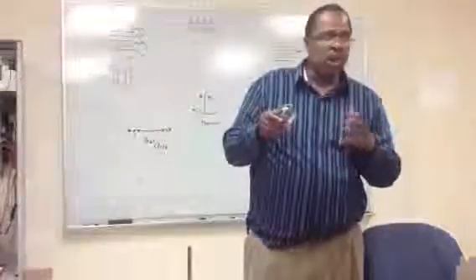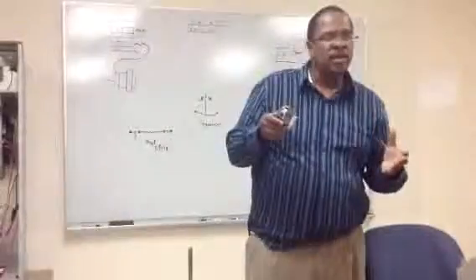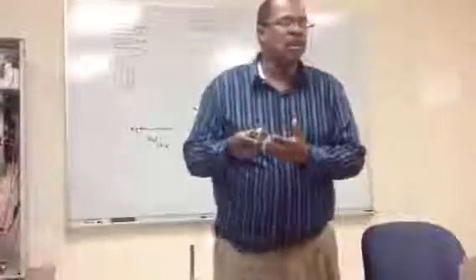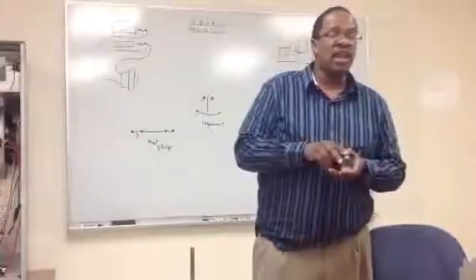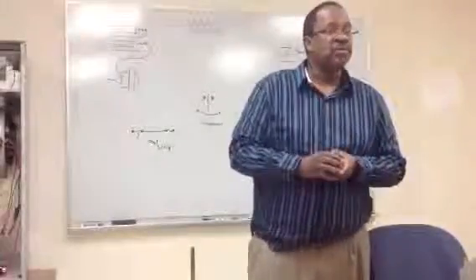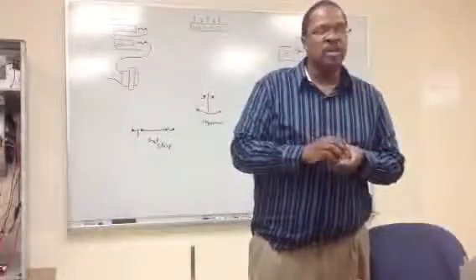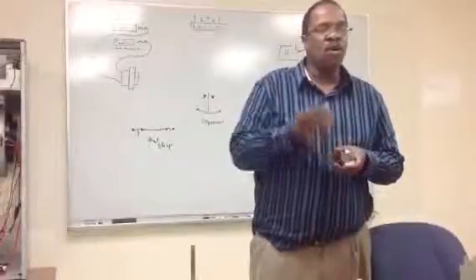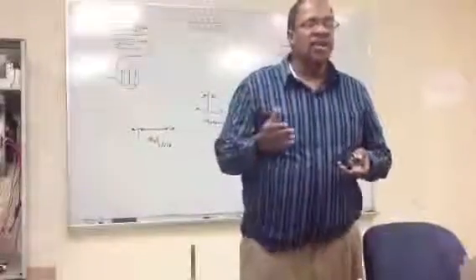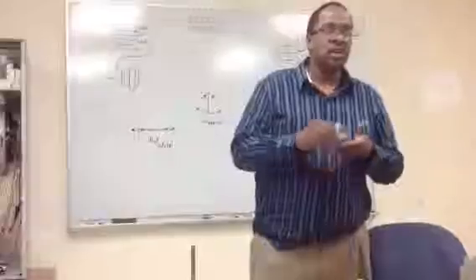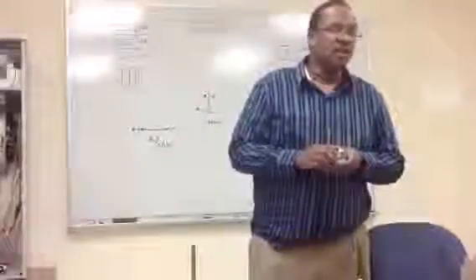You need to read whatever transformer it is, make sure you wire it up correctly. Some will have a 120 tap, and they have different colors for each tap on the ones that use wires. So you need to be sure, because if you wire up a transformer wrong on either end, you can cause your controls or the transformer itself to blow.